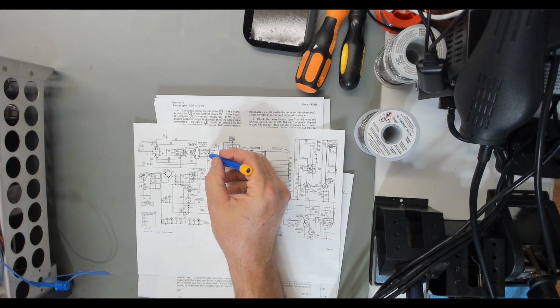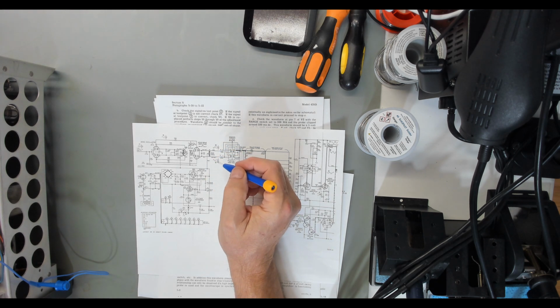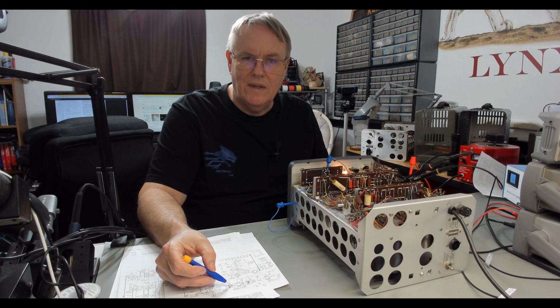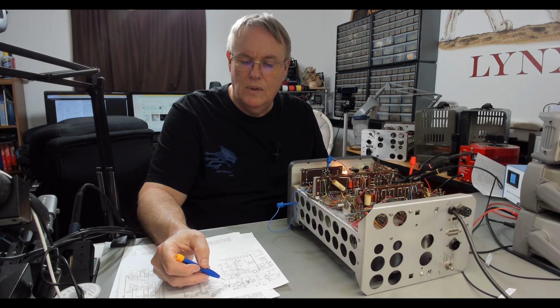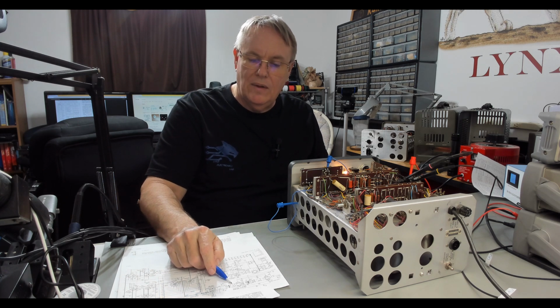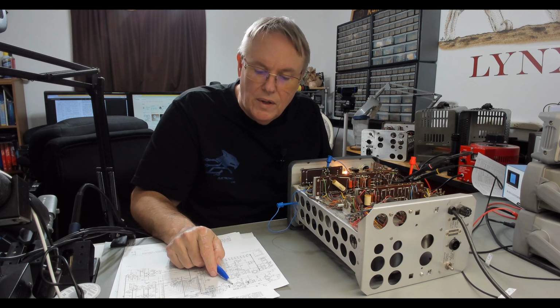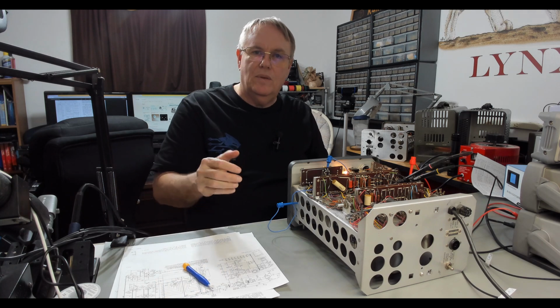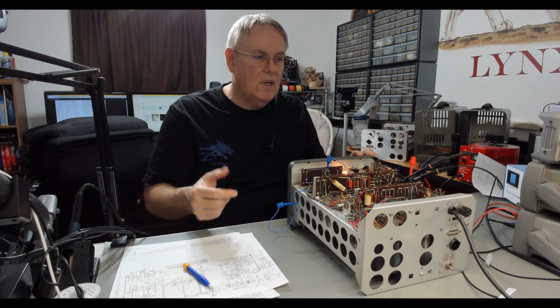I'll check this capacitor just to make sure it's not causing a problem, but I don't know what it would do. Seems like if it shorted, it would take both of them down. If it went open, it wouldn't have an effect at all. But I'll check that if I've got an imbalance here. Let me get set up, check that, and we'll see what we come out with, whether pin 1 and 6 look balanced. So it's going to be a much higher signal, 12 volts.